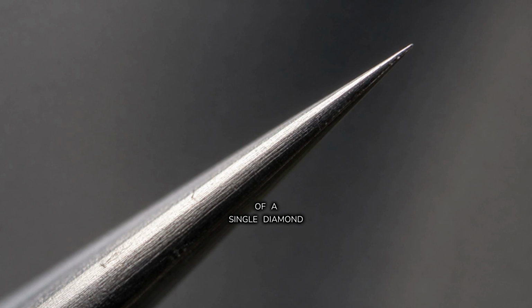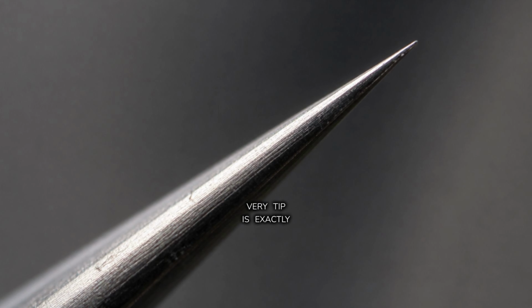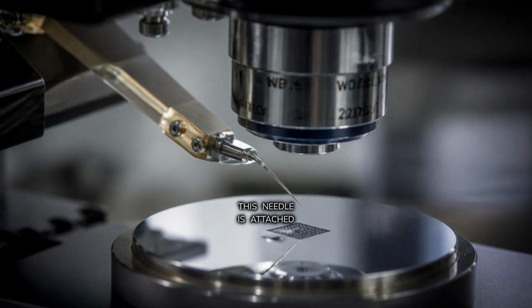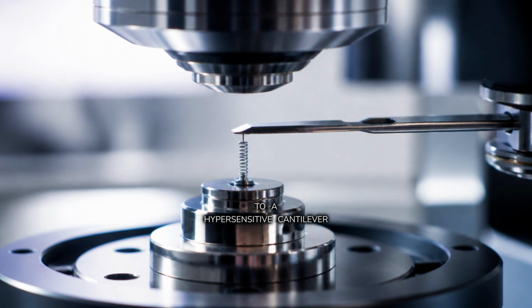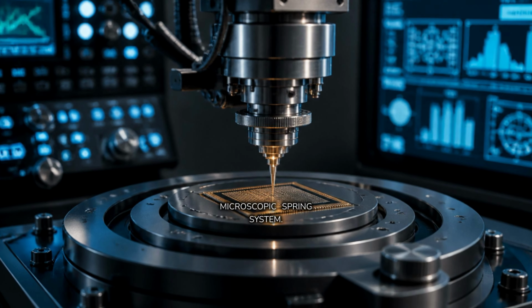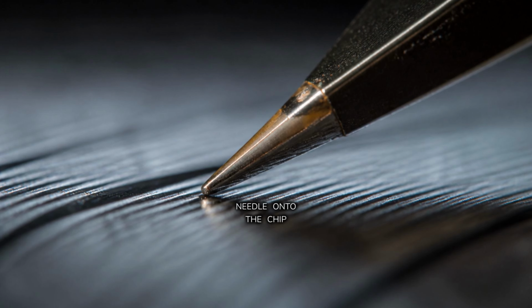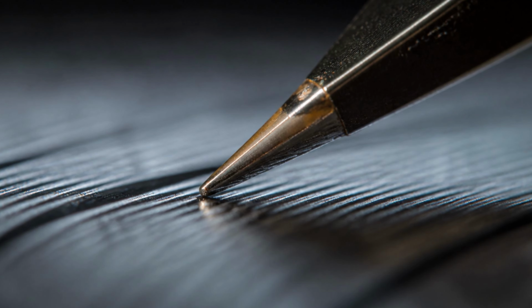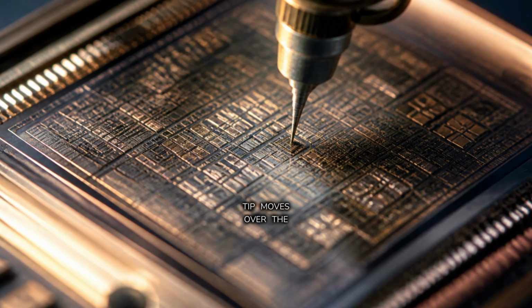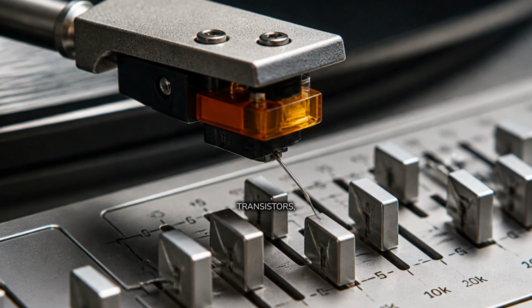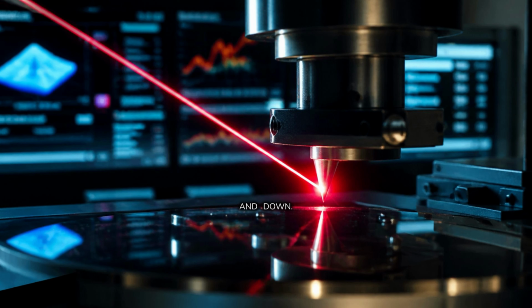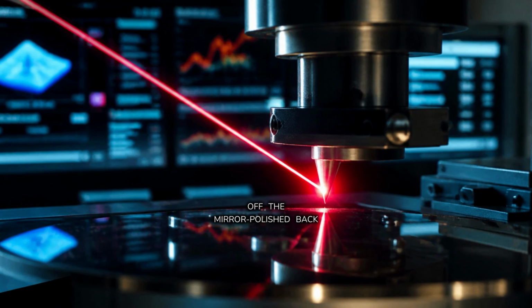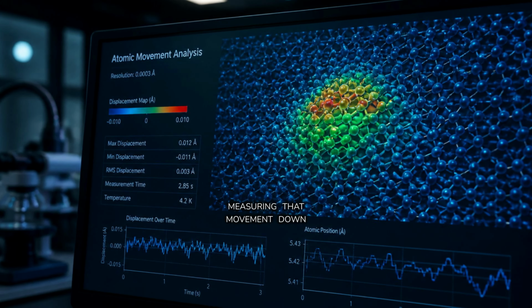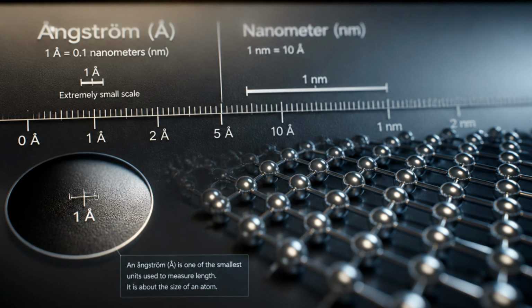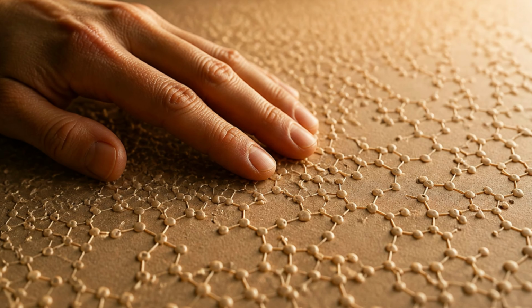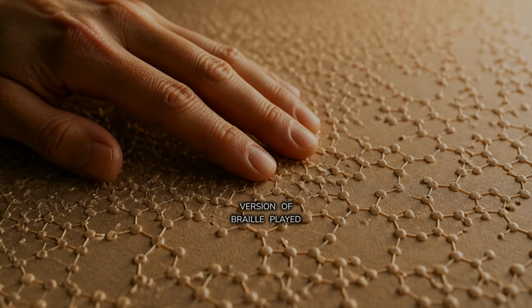Imagine a needle made of a single diamond, sharpened down until the very tip is exactly 1 atom wide. This needle is attached to a hypersensitive cantilever beam balanced by a microscopic spring system. The machine lowers this needle onto the chip and drags it across the silicon surface. As the single atom tip moves over the 4 nanometer valleys and peaks of the printed transistors, the needle deflects up and down. A precise laser bounces off the mirror-polished back of the needle tip, measuring that movement down to a fraction of an angstrom. 1 angstrom is 0.1 nanometers. It is the ultimate version of Braille, played at the atomic scale.